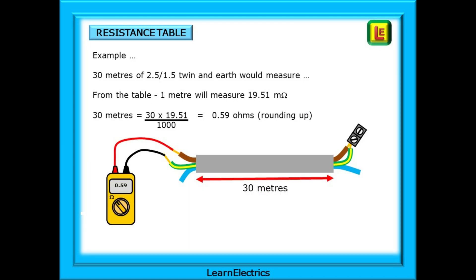Here we have a 30 meter length of 2.5 by 1.5 twin and earth cable. According to table B1, this will measure 19.51 milliohms for every meter length. Simply multiply 19.51 milliohms by the 30 meters and we have an answer of 585.3 milliohms for the whole 30 meters. Now to convert this to ohms, divide by 1,000 and we have 0.59 ohms when we round up.